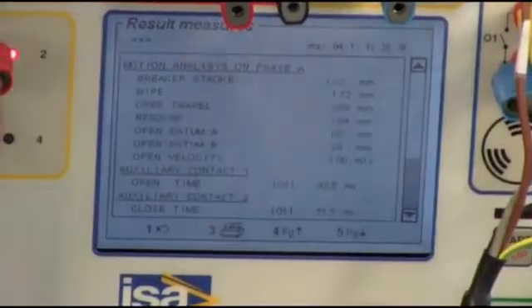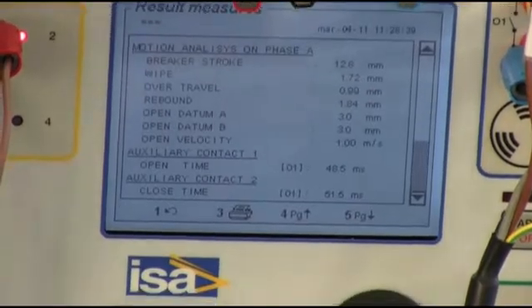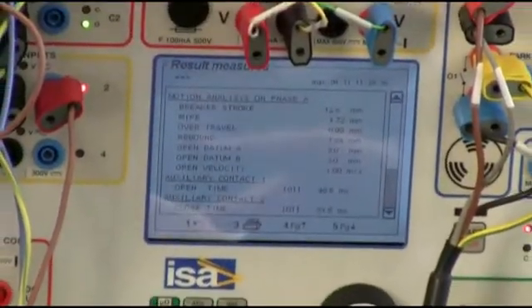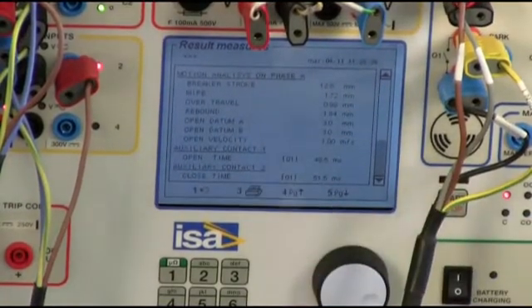And also the wipe is a little bit different, it is 1.72 millimeter and you can appreciate that given the type of circuit breaker where the total stroke is 13 millimeter, this is an important figure.